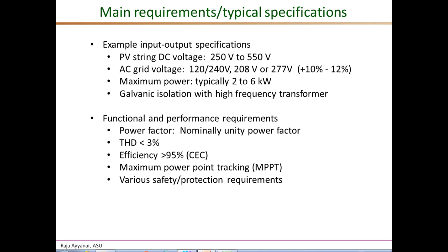Coming to the functional and performance requirements, the string inverters, at present, invariably operate as controlled sinusoidal current sources, operating exactly at unity power factor. The smart inverters in the near future would be required to operate at arbitrary power factors and to provide reactive power support to the grid. But as of now, all inverters operate exactly at unity power factor.